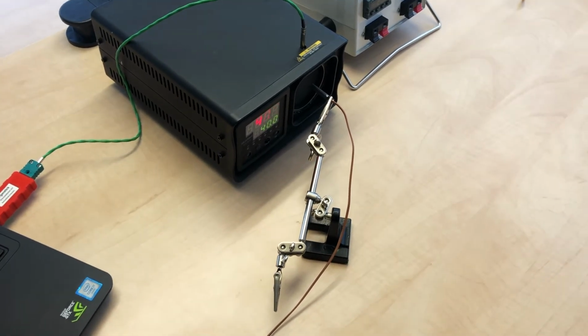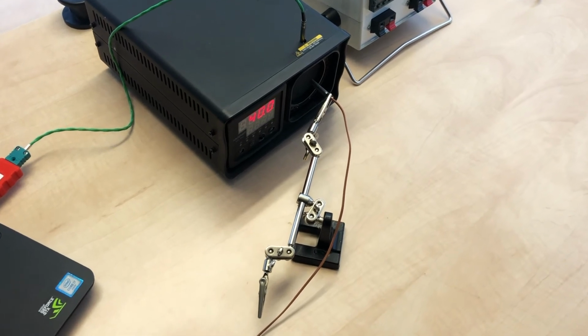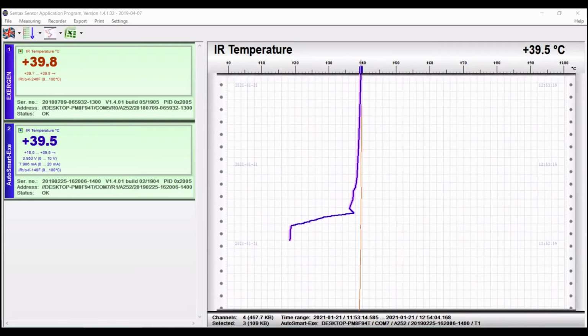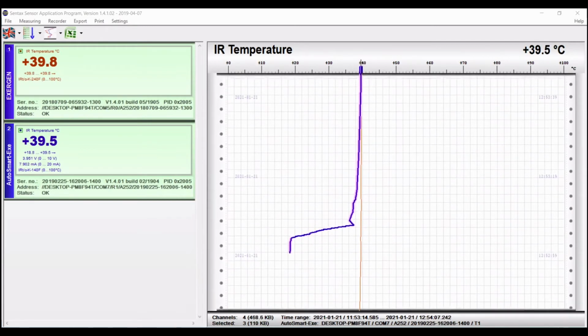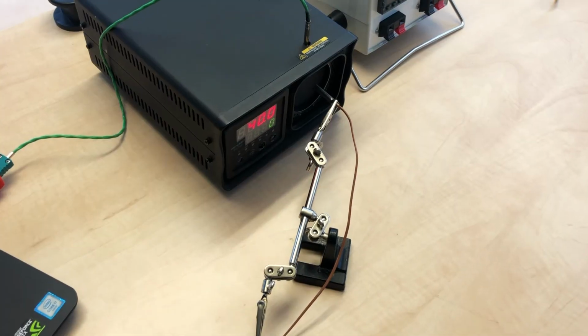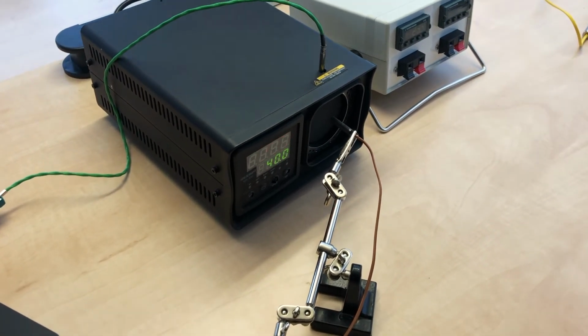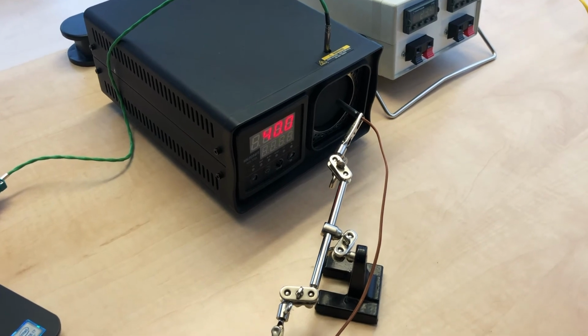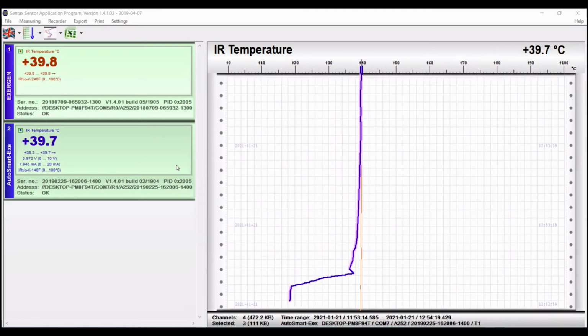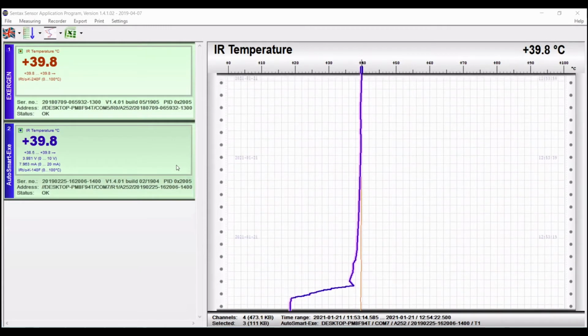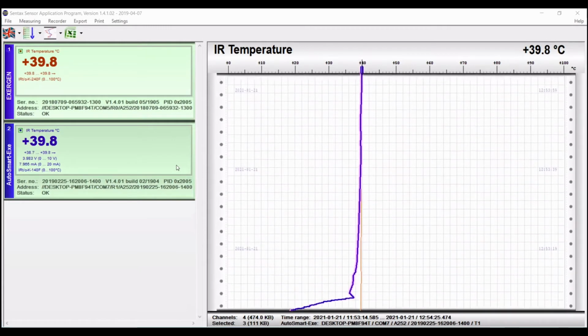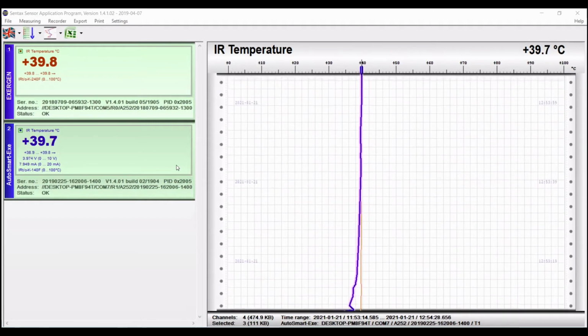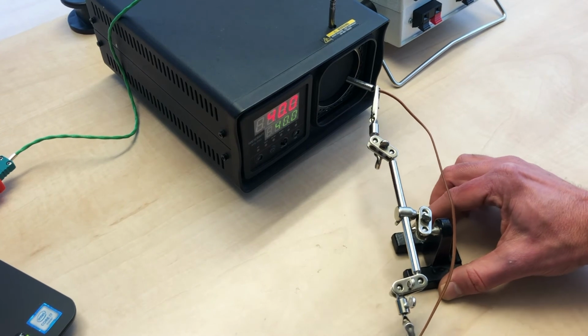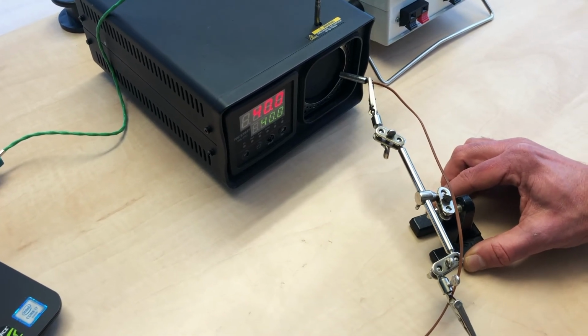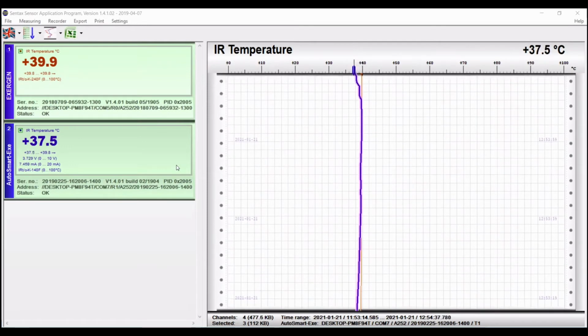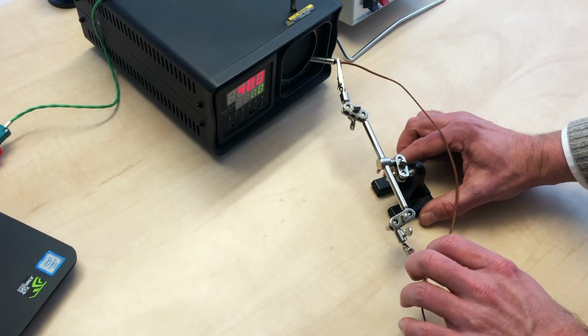In customizing an AutoSmart IRtc, there are several things that you can customize. You can customize the output, you can customize the temperature range, but what makes this software so useful is that you can adjust the sensor reading to match the reference sensor. Let me demonstrate how this works. You see, by the way, on the screen that the two measurements are really nicely aligned right now. But in this case, just for the sake of example, I'm going to put the sensor at an angle. Let's say you have an application where the sensor is maybe measuring obliquely.